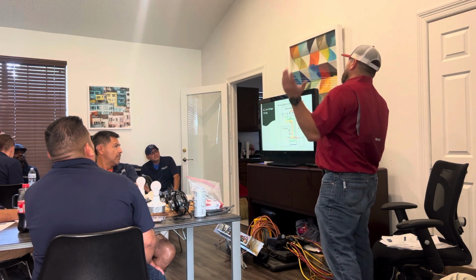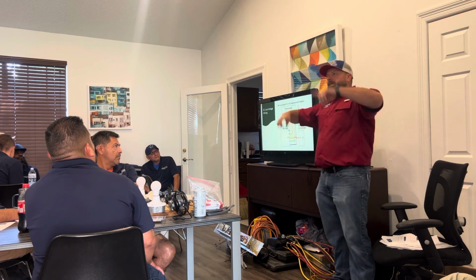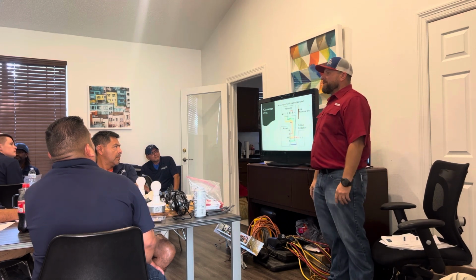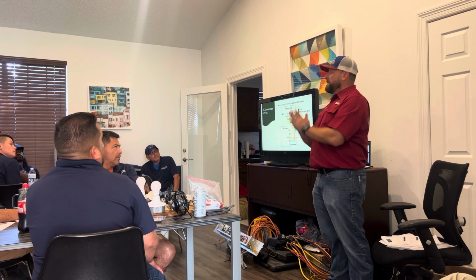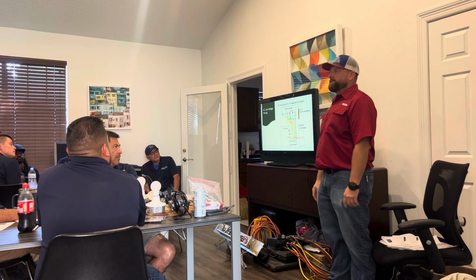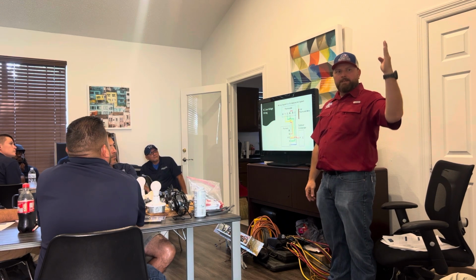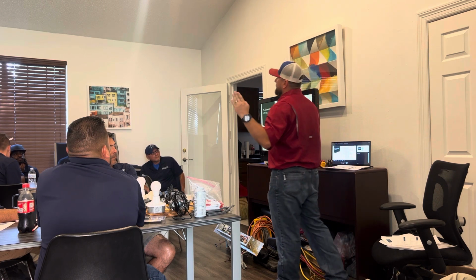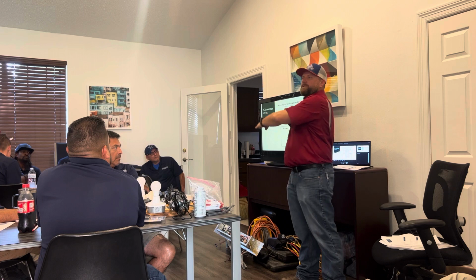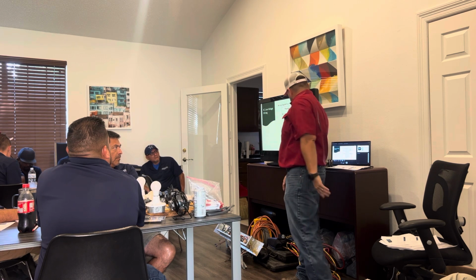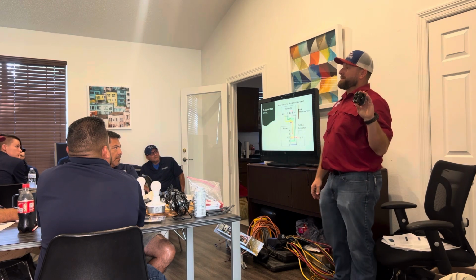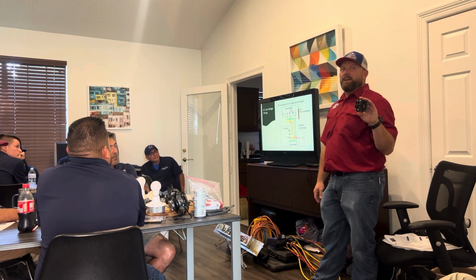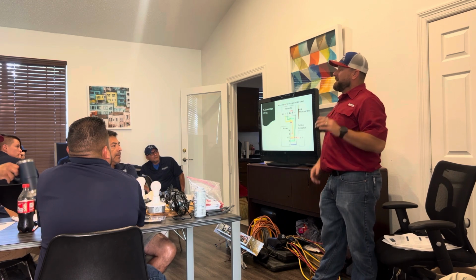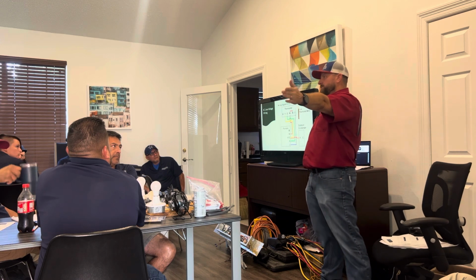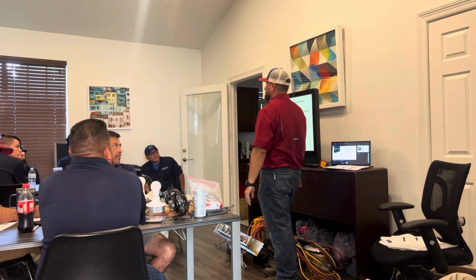24 volts, remember when I was talking about the thermostat being the conductor of that orchestra? All that thermostat is doing is managing that R wire. That thing is hot all the time, 24 volts. So if it says, I'm ready to cool, I've got to send power over to yellow, the Y, to tell that outside contactor to come on.